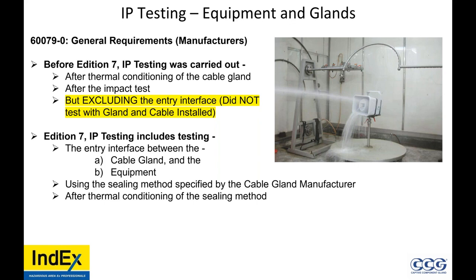Now, edition 7 called for IP testing the interface, so the cable gland threading into the equipment had to be installed. So if they said it's IP66, it would call for the use of an IP washer at all times. You always require an IP washer to get IP66. Now, the use of a sealing method shall be specified by the gland manufacturer, but it's the equipment manufacturer having their equipment tested. Do they care about which gland is used? No, they don't consider that. If the gland manufacturer is having their gland tested, what device is it being tested on? There are hundreds of thousands of combinations. So are those tests all possibly done? Of course not.